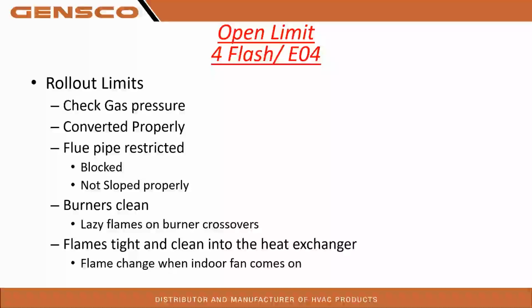So we're going to look at the flames tight and clean to the heat exchanger. So in that situation with a negative heat exchanger with positive air around it, if you had a crack in the heat exchanger or compromised heat exchanger, wouldn't you see flame disruption? Because now you have positive air pushing on negative space. And that's when you would see rollout issues. So if that heat's coming forward of that heat exchanger, it's got to be something with the airflow pattern in the heat exchanger itself, right? Something is happening there.